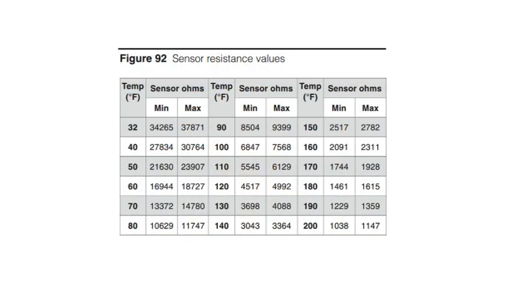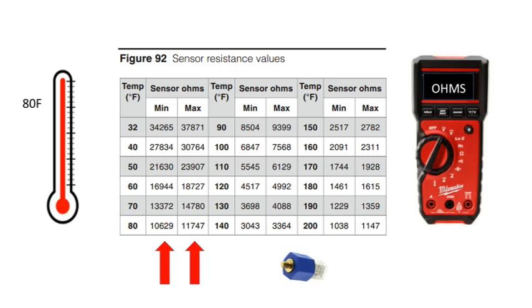Now that we have a pretty solid grip on the nature of this error, there are a few other diagnostic tips we can take a look at. First, these sensors all have identical resistance values, and you will see this chart in each of the manuals. It represents the resistance you should be seeing at varying temperatures. If you take an ohm reading on one of these sensors with a given temperature value of, let's say, 80 degrees, you should see between 10,629 and 11,747 ohms. If it's not in that range, replace the sensor.